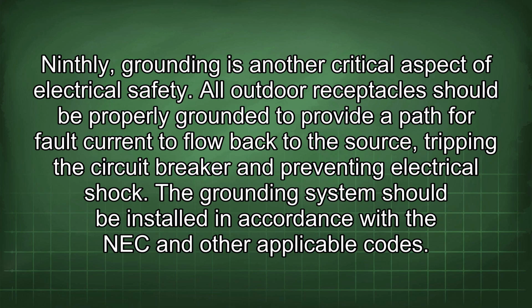All outdoor receptacles should be properly grounded to provide a path for fault current to flow back to the source, tripping the circuit breaker and preventing electrical shock. The grounding system should be installed in accordance with the NEC and other applicable codes.